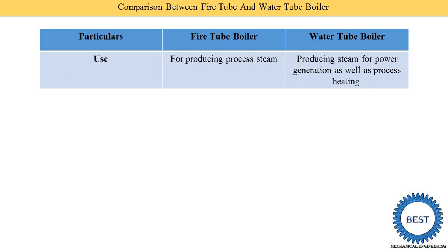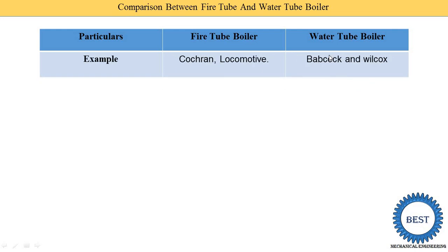Next point is the use of the boiler. Fire tube boiler is used for producing process steam — meaning steam produced by the fire tube boiler is used in different textile processing or different industries — it is not used for power generation. In a water tube boiler, steam is produced for power generation as well as for processing. Meaning water tube boiler is used in power plants as well as for processing. The last point is examples: fire tube boiler examples are the Cochran boiler and locomotive types. Water tube boiler example is the Babcock and Wilcox boiler.